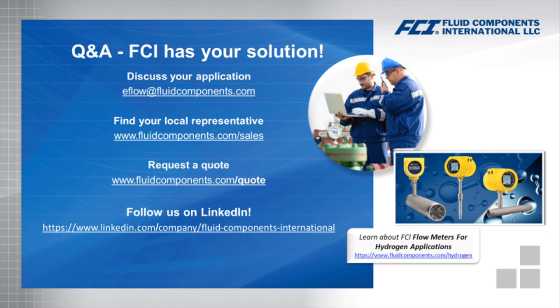All right, Art, next one here. What kind of question should I ask a manufacturer to ensure a flow meter is properly calibrated for hydrogen? Capability. Questions we typically like to see, and think you should ask about, are how applications are evaluated, given all your process conditions, can that measurement be made with the technology? The type of calibration, how is it performed? Is it going to be an actual gas? Is it going to be some type of equivalency method? Things of that nature.